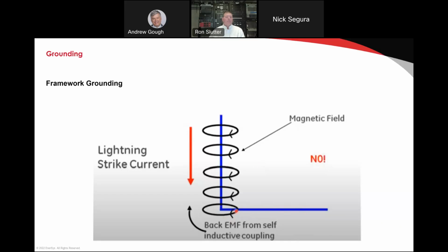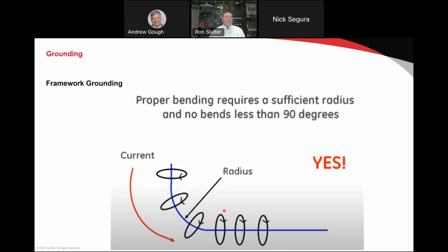Okay. So what do we do to install grounding properly? We put a radius on all of the bends. So in your facility, you should have a nice 12-inch radius on all of your grounding. If it's a U, it is a choke. If it is a 90-degree bend, it is a choke. And all of that should be in the direction of flow. Notice the direction of current flow here.